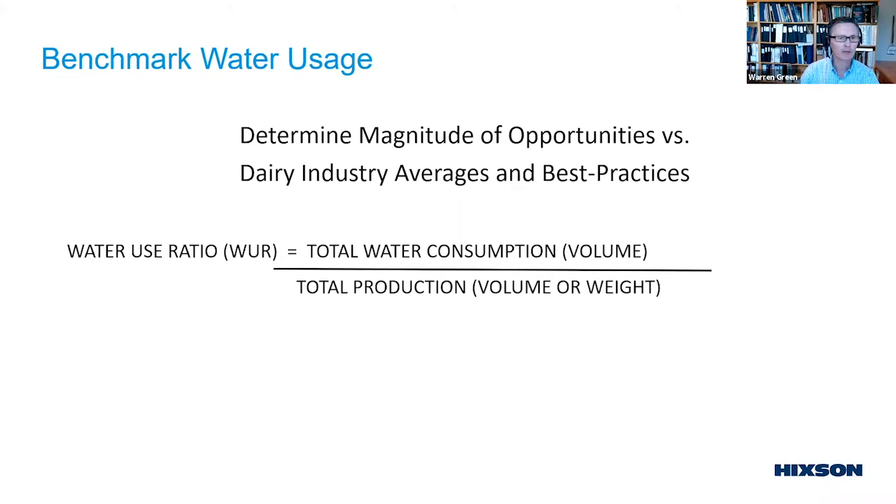Looking at Hixson's statistics: for fluid milk, the average across all plants worked with is about 1.7 gallons of incoming water for every gallon of milk that leaves the plant, with a range of 1 to 2 gallons per gallon. Combination dairies, pure cheese production, ice cream plants, and other segments each have their own benchmarks, confirmed by global industrial data.